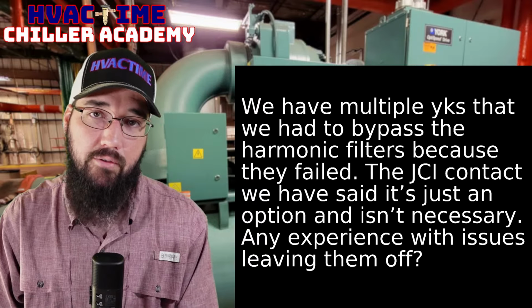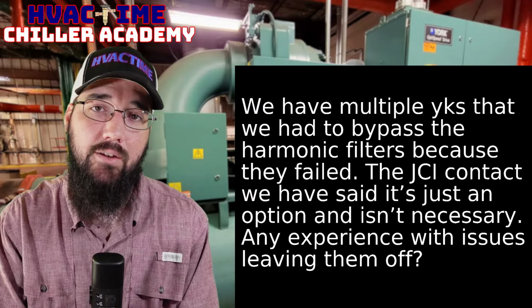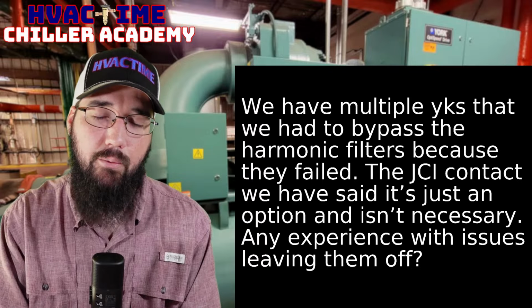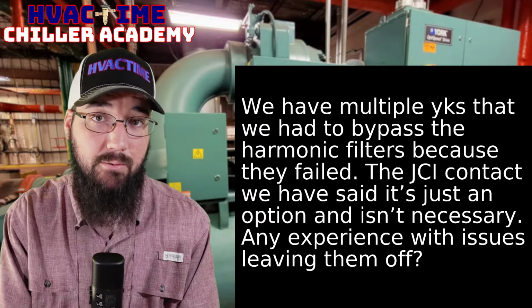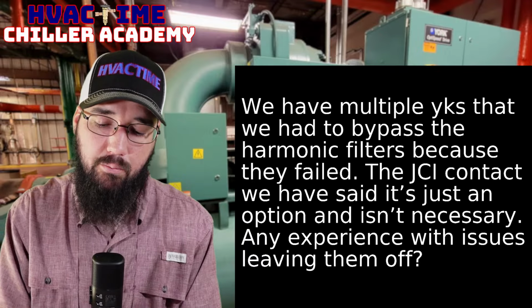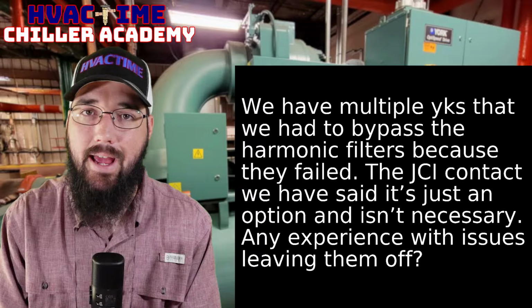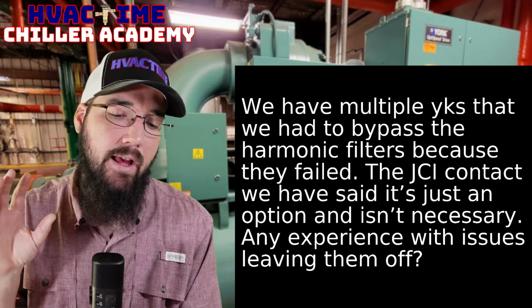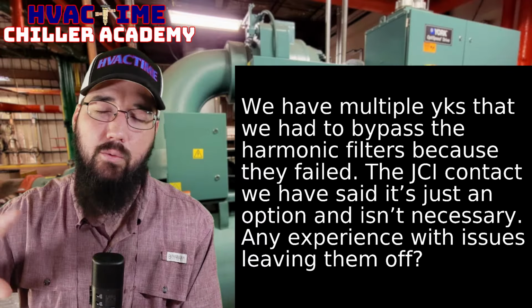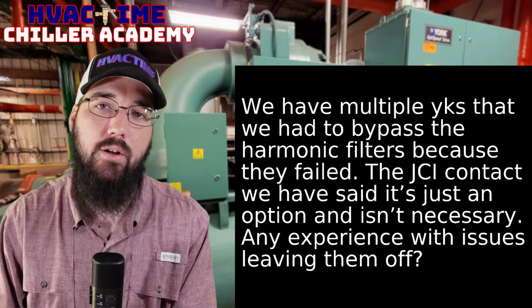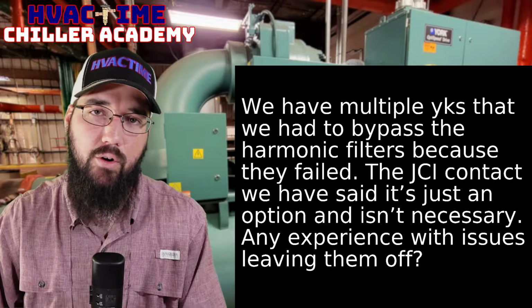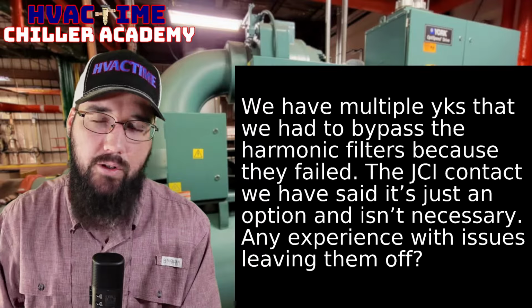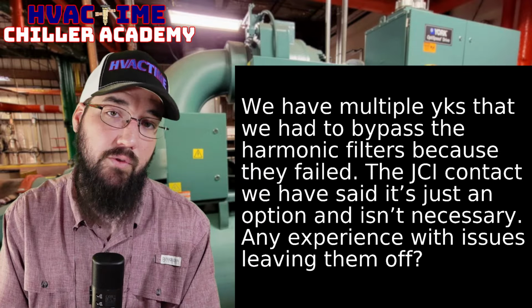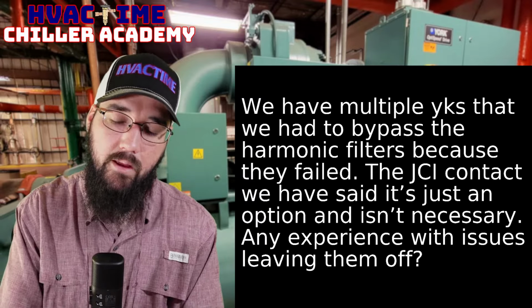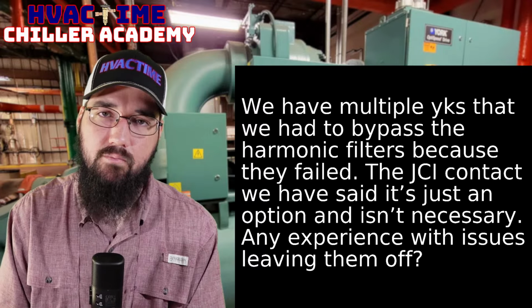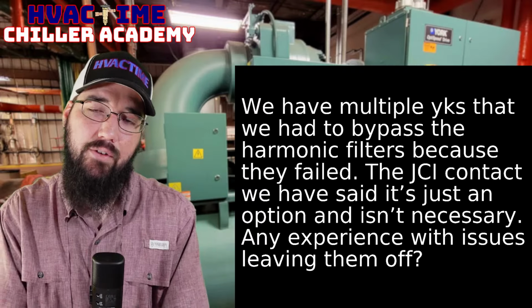Now, the whole point of the harmonic filter is to help compensate for that and to get us an even cleaner source. But the line reactor that we already have as a default component, which has to be there, already does a lot of that. You'll also see it referred to as a line inductor, line reactor. They're interchangeable terms from our standpoint. I've had people get super technical with me on this, and there are cases where it matters depending on what sector of the world you work in. But from a general standpoint, us as guys working on chillers, it doesn't really matter to me which you call it, because you'll see manufacturers call it both ways. Some of them will say reactor, some will say inductor. Either way, that needs to be there because that inductor core is inducing a lot of that static out of the feed coming into the compressor.